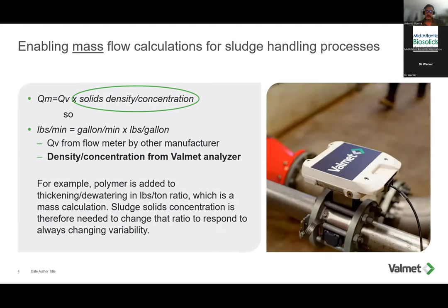Specifically in dewatering, we're using chemicals, polymers, and historically we're doing everything by volumetric flow. However, polymer is dosed in pounds per ton. So in order to work with pounds per ton, you should really be working with mass flow and not volumetric flow. Typically, for example, on a dewatering system, you'll have a flow meter feeding the system. And then by adding a density or concentration meter, you have everything you need to start using mass concentration and mass flow to optimize your process.